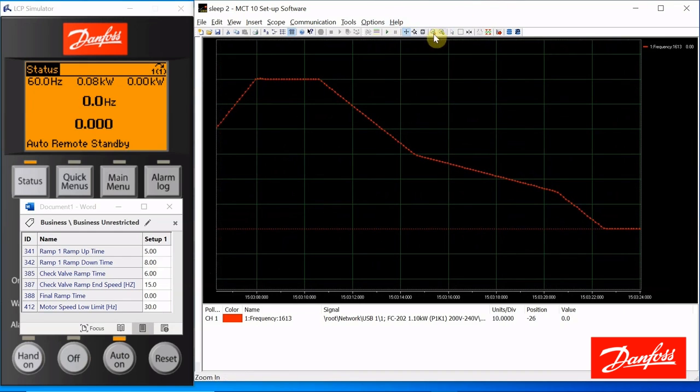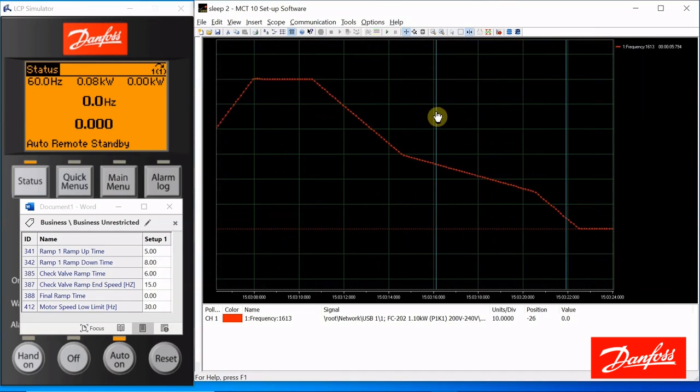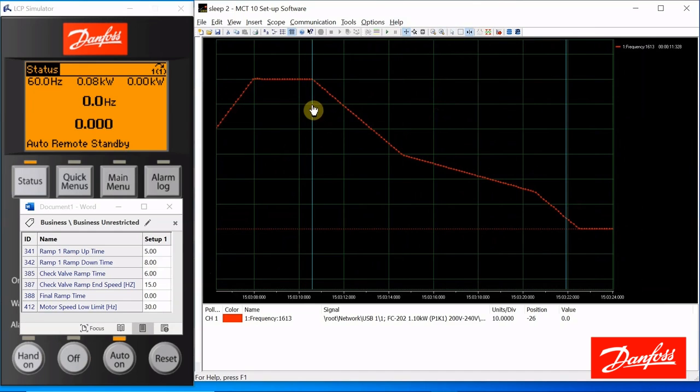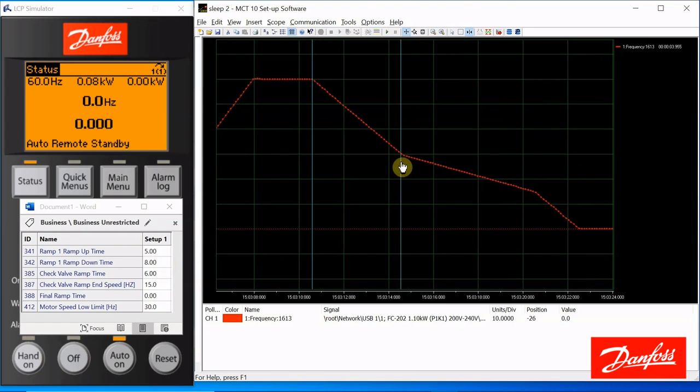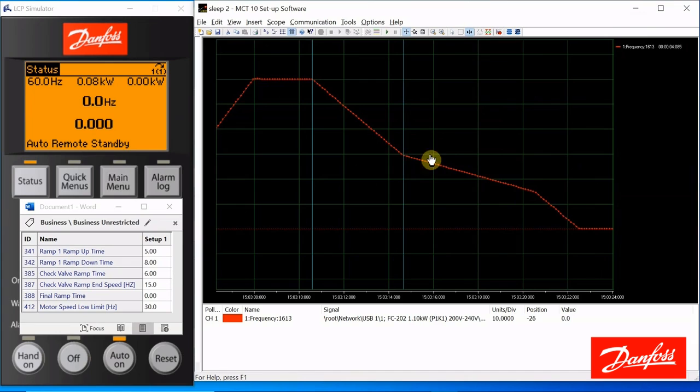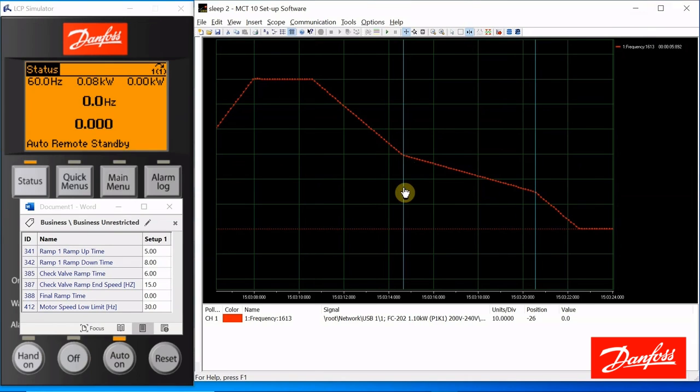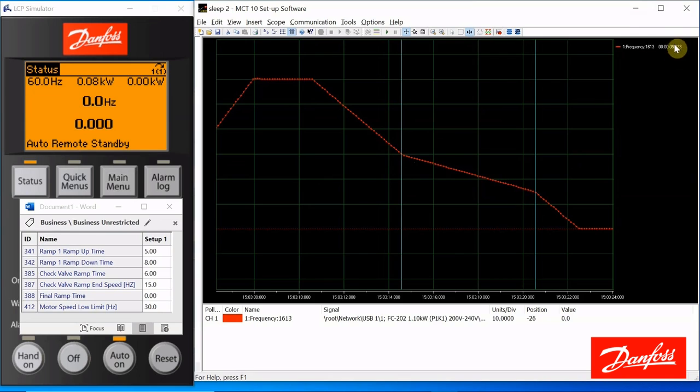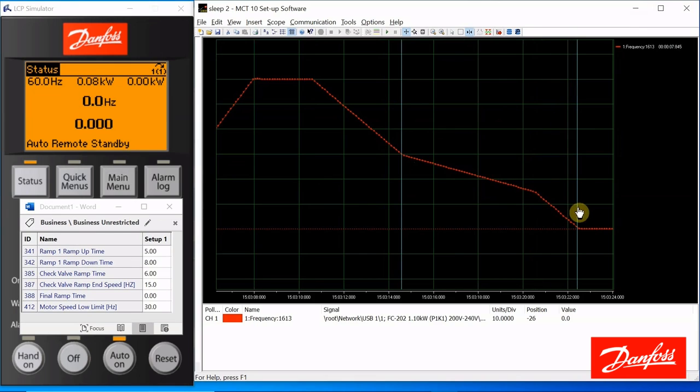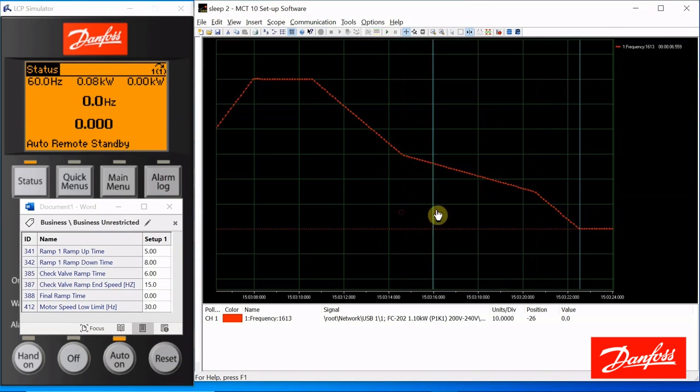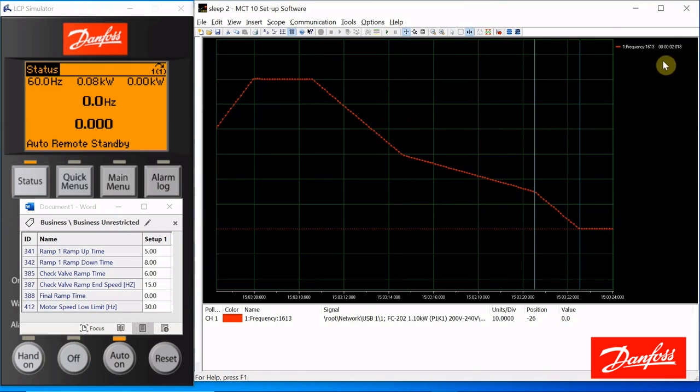Let's look at our cursors. So this is 60 hertz. If it takes 8 seconds to get from 60 to 0, it should take about 4 seconds to get from 60 down to 30. And then we have here our check valve ramp time. We said give us 6 seconds. That's about what it is to get from 30 hertz down to 15, and then from 15 down to 0. That should be about a fourth of 8, right? About 2 seconds. There you go.